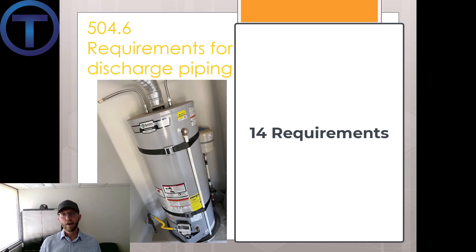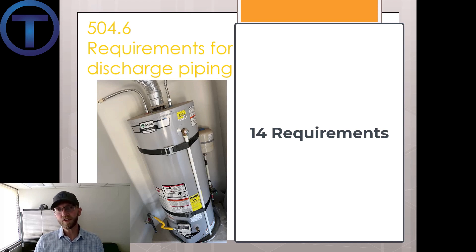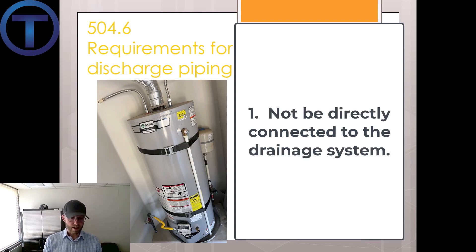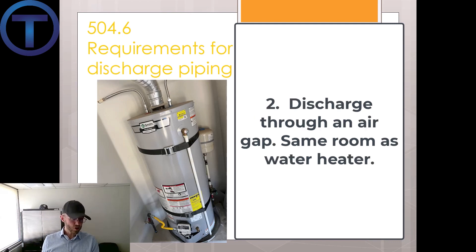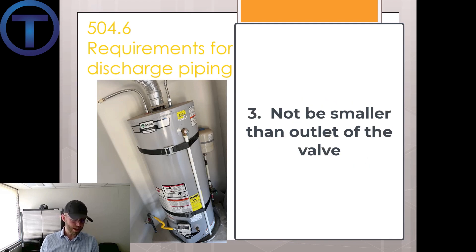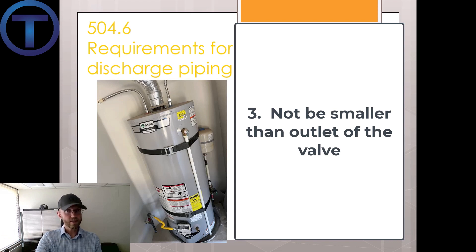Coming from the temperature pressure relief valve is a discharge pipe, and 504.6 gives us 14 important points about the installation of this discharge pipe. Number one: it's not to be directly connected to the drainage system — this is an indirect waste. Number two: discharge through an air gap. Number three: not smaller than the diameter of the outlet of the valve served — three-quarter inch typically has to stay three-quarter inch all the way down.